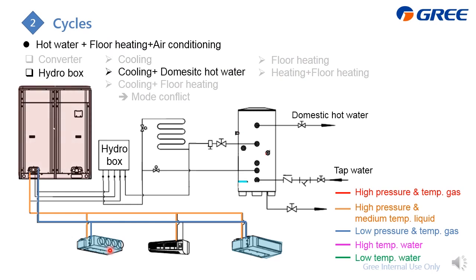And if at the same time we require the domestic hot water, then we need to send the hot gas, which is from the third piping, to this hydro box. After releasing heat, this hot gas will become liquid. And then we can combine these two liquids, one from the hydro box, the other from the indoor units. Combine them together. After that, the hydro box can generate the hot water. From the connection, it goes to this, and for DHW, we send the hot water here to heat up the DHW. Then it cools down and goes back to the hydro box. So from this one, it is already heating up the DHW.